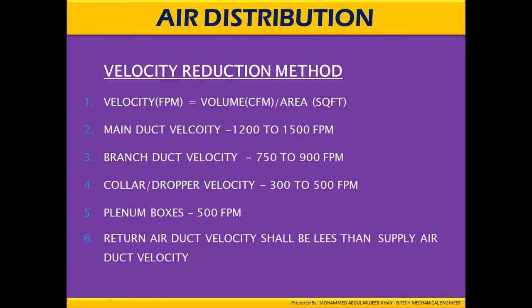The velocity reduction method: velocity is measured in FPM (feet per minute), which equals volume divided by area. Main duct velocities should be between 1,200 to 1,500 FPM. Branch duct velocities should be between 750 to 900 FPM. Collar drop velocity should be between 300 to 500 FPM. Plenum box velocities should be considered at 500 FPM. Return air duct velocity shall be less than the supply air duct velocity.